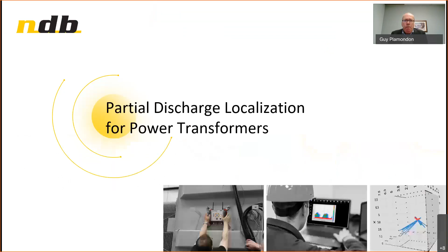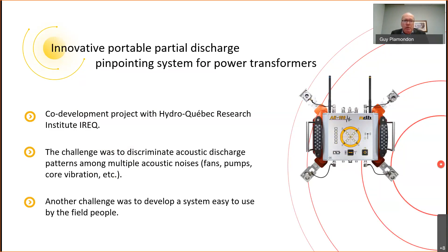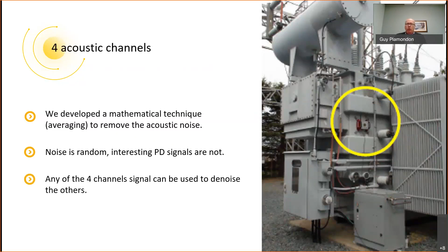The challenge was to discriminate the acoustic discharge patterns among multiple acoustic noises generated by the transformer accessories. So another challenge was to develop a system easy to use by the field people. To do so, we used 4 acoustic channels, and we developed a mathematical technique that we call averaging to remove the noise from the transformer's accessories. Because the noise is random, the partial discharge signals are not. So any of the 4 channel signals can be used to denoise the other.